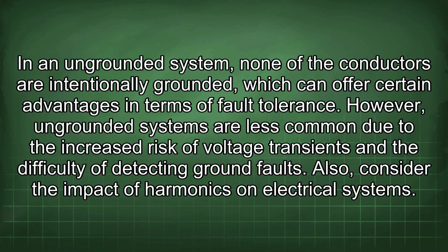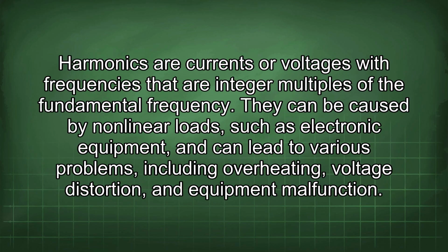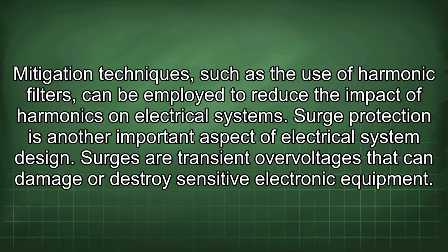ground faults. Also, consider the impact of harmonics on electrical systems. Harmonics are currents or voltages with frequencies that are integer multiples of the fundamental frequency. They can be caused by nonlinear loads, such as electronic equipment, and can lead to various problems, including overheating, voltage distortion, and equipment malfunction. Mitigation techniques, such as the use of harmonic filters, can be employed to reduce the impact of harmonics on electrical systems.